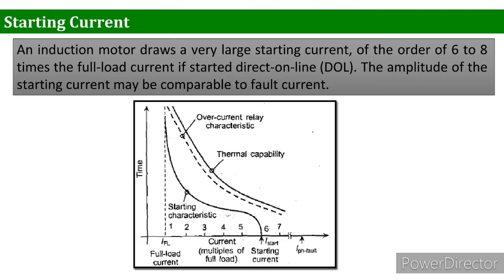As we all know, an induction motor draws a very large starting current, like 6 to 8 times the full load current. So if the motor is started direct online, that is DOL, the amplitude of the starting current may be comparable to the fault current. And this is an interesting question also. Therefore, the overcurrent protection provided to the motor must be able to discriminate between a genuine fault and an overcurrent due to the starting of the motor.